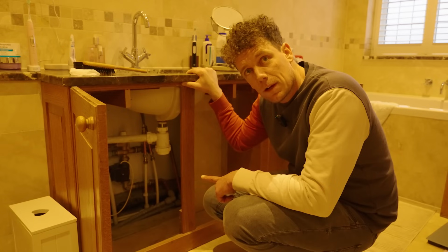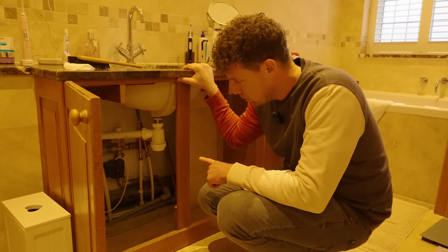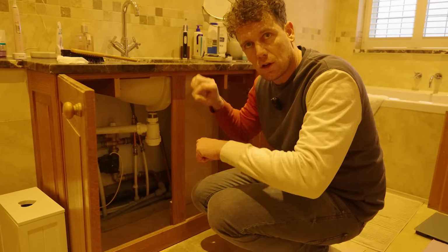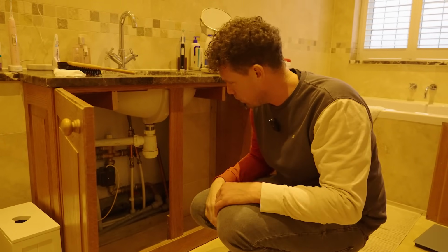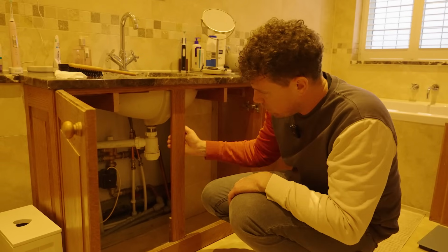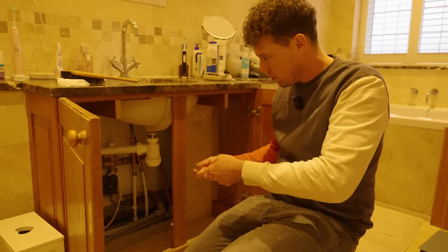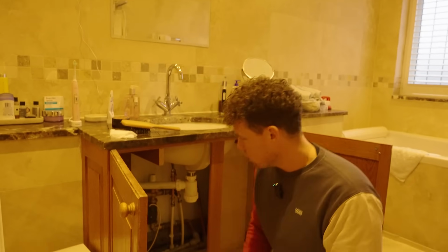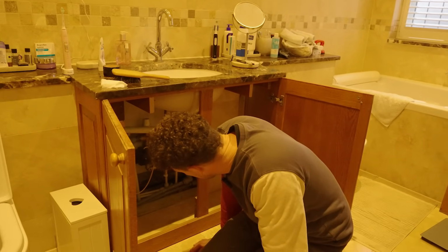He has 22mm plastic underfloor heating installed. So that doesn't sound right, because you can't bend it, so you can't have that sort of underfloor. So I'm not too sure what this does, unless it tees off and whatever it is, it's been botched together. It's not been installed properly at all. Let's have a look under here.